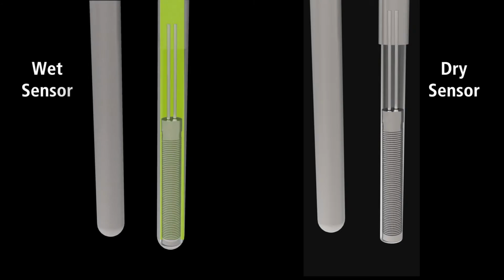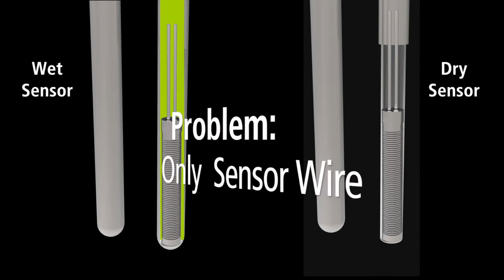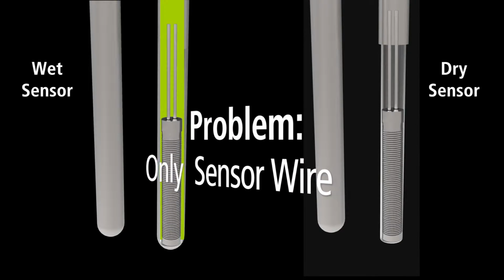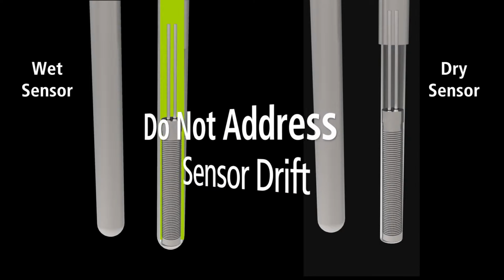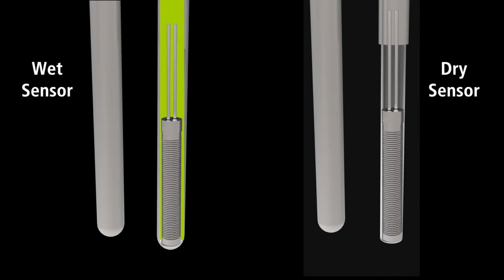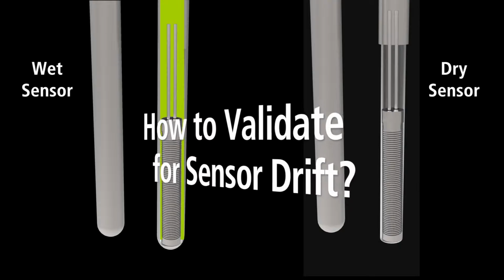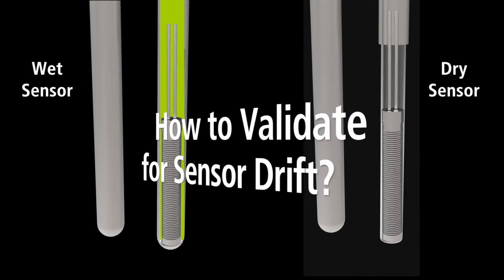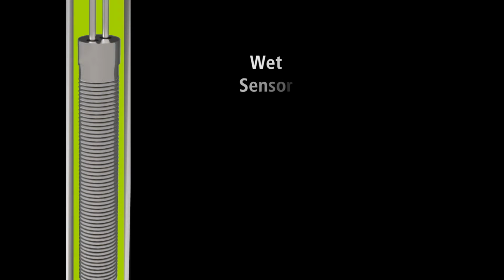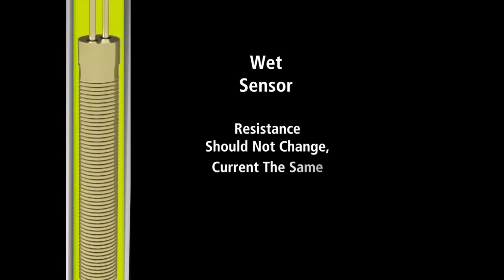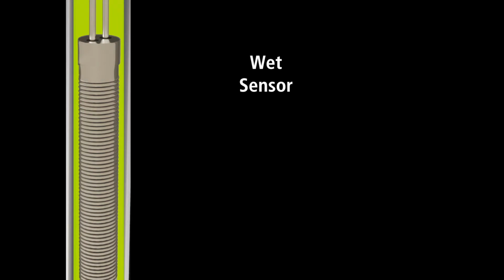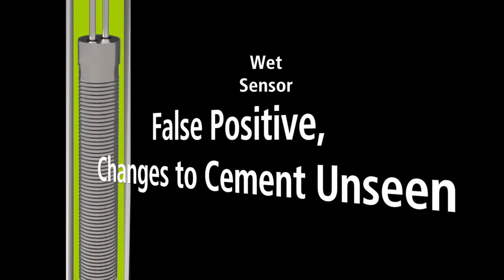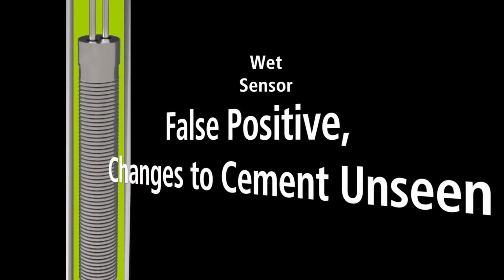The problem with both methods is that they only measure the characteristics of the internal sensor windings and do not address sensor drift. The big question is, how can you validate a sensor that will drift out of spec due to the very nature of its mechanical design? The resistance of the platinum wire shouldn't change, and the current running through the sensor might be the same, both of which would validate OK. This is a false positive, as the drift inherent in a wet sensor design would remain unseen.